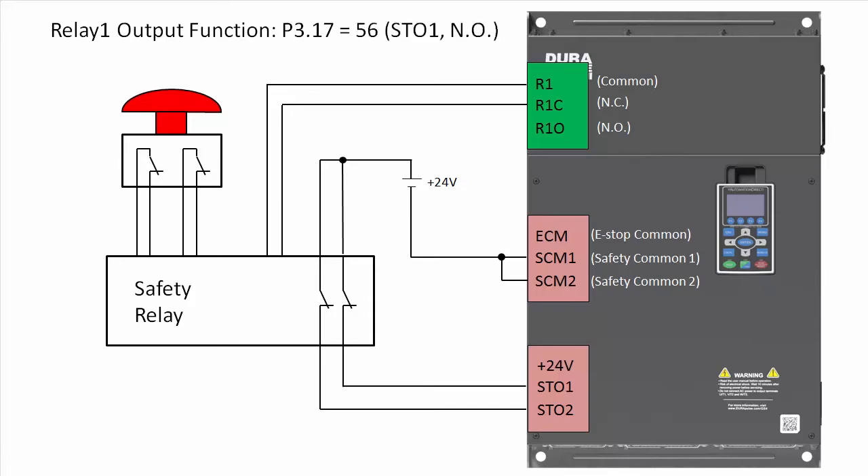Entering a value of 56 says to monitor STO 1 and make it normally open. A value of 57 says to monitor STO 2 and make it normally closed. Of course you can switch the wire to normally open or normally closed to invert that if you need to. You can also use relay 2 if you need it — just set parameter 3.18 to tell relay 2 what to do.